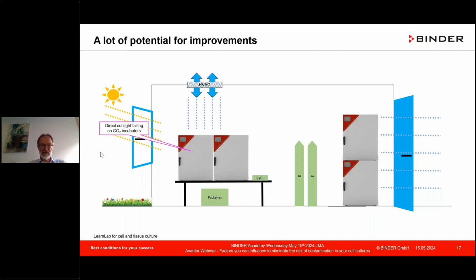Number one, we have direct sunlight falling on CO2 incubators. You are heating it up, and that heat will disturb the temperature inside, usually 37 degrees C. You will have a temperature overshoot, and that is not good, neither for the incubator nor for your cell lines. So that is one point to have on your radar screen. Drafty doors when the door is open. Always very, very simple things. And when entering the room, open the door quickly, close it, and that's it.